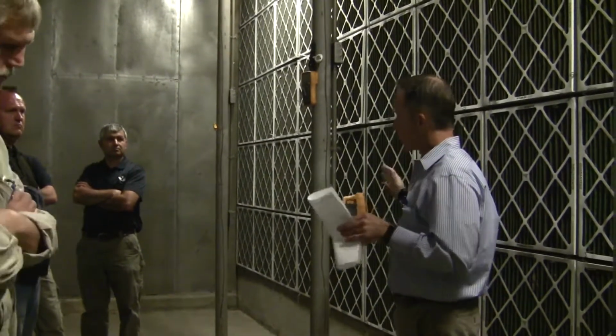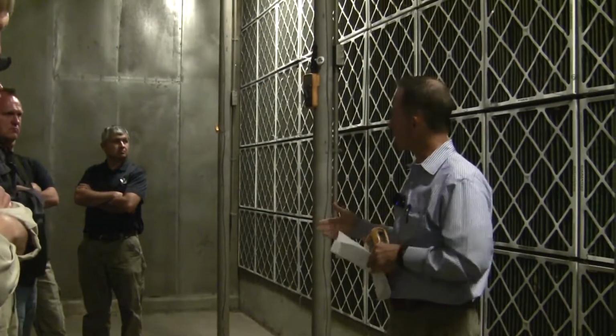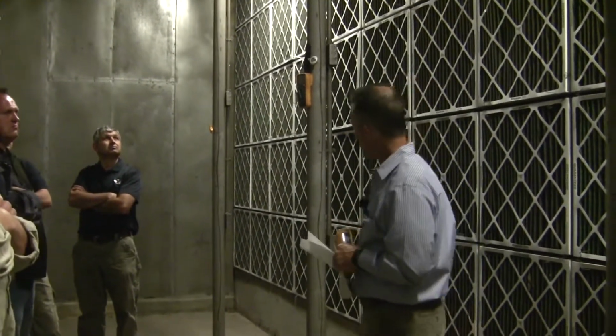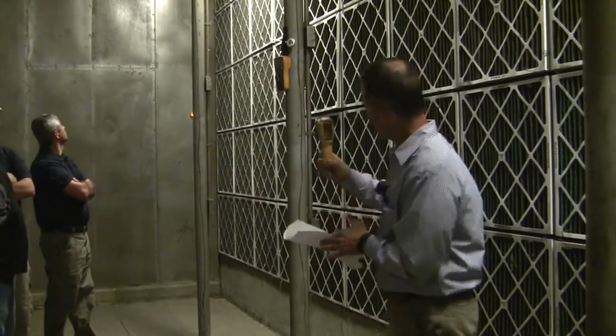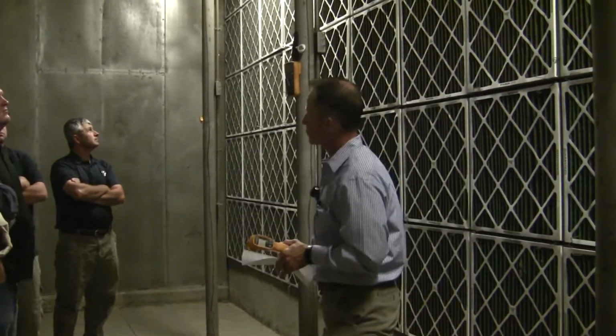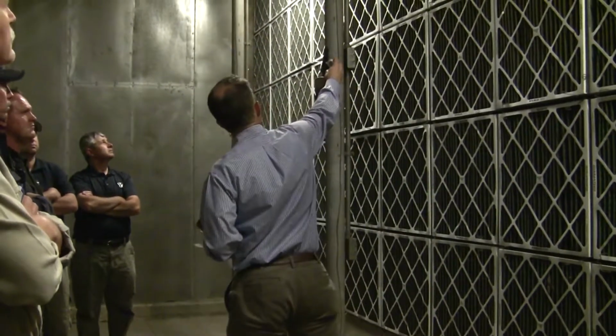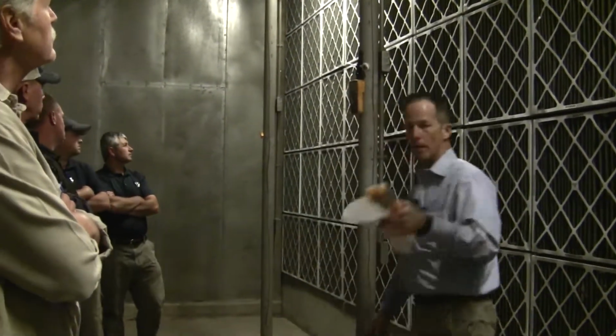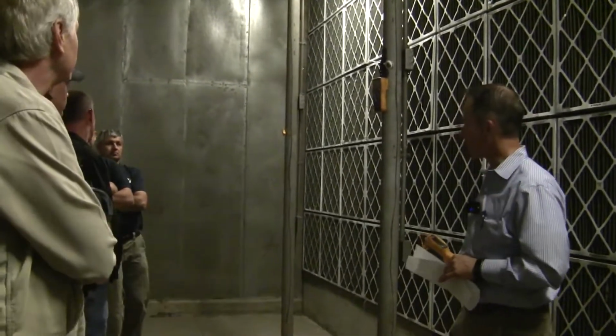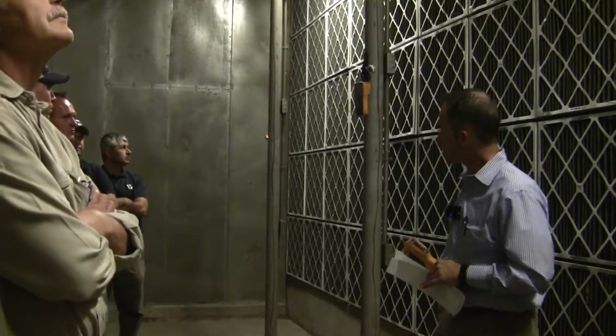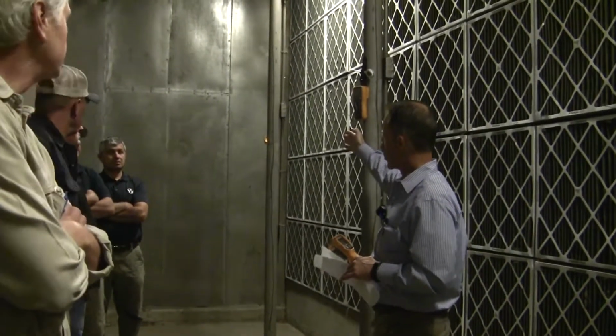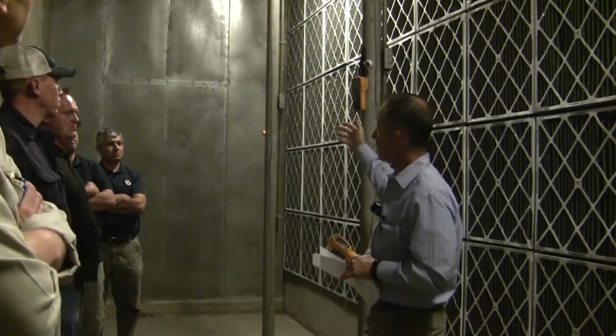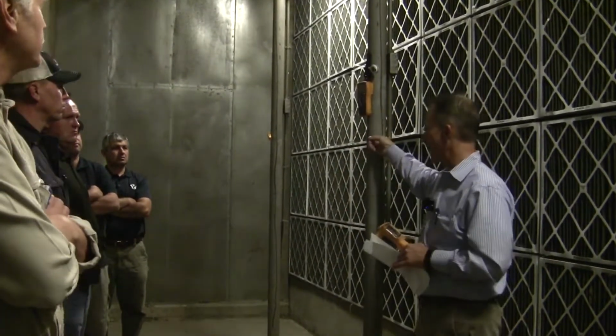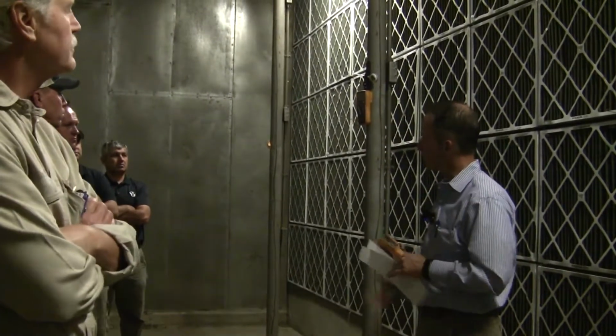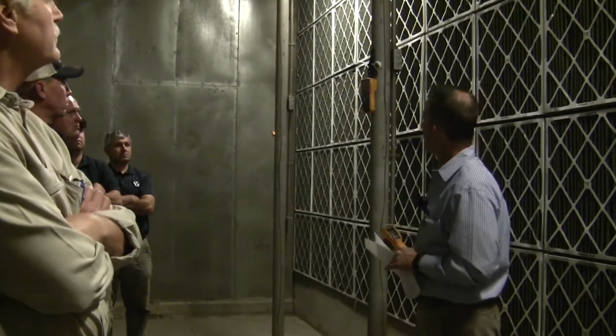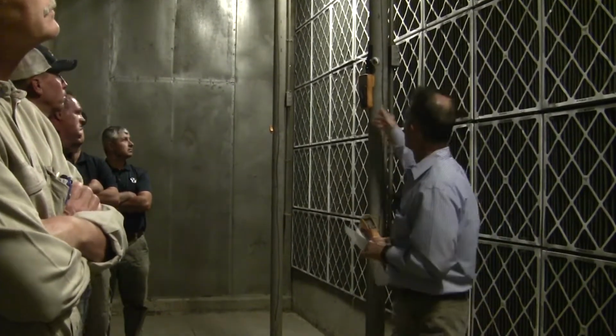Room sensors, we can get away with those. They don't really add up as much, but something like this does. So the last measurement, 72.6 on both of those, and then we're 74 on the little lollipop. Okay, pocket thermometer, and that one's 73.4. But could that be accurate? Right there it could, sure, because we're not in the same place, right? You could always take all of your sensors, put them right together, see how close they are, come up with an average, and then use that. Or pick one that you think will be the best. All right, let's go to the next area.